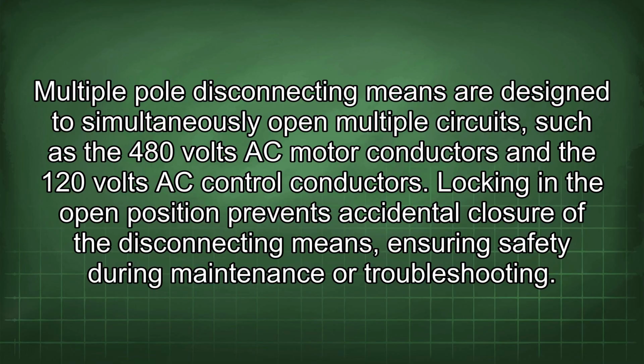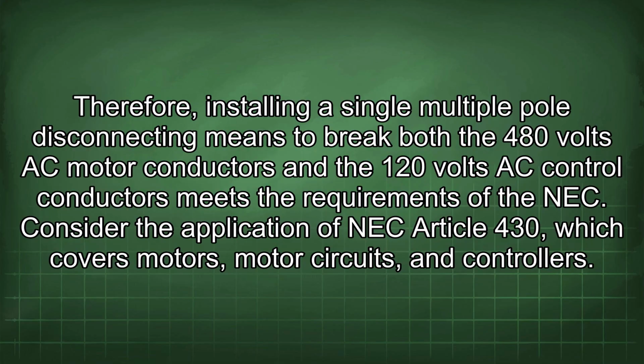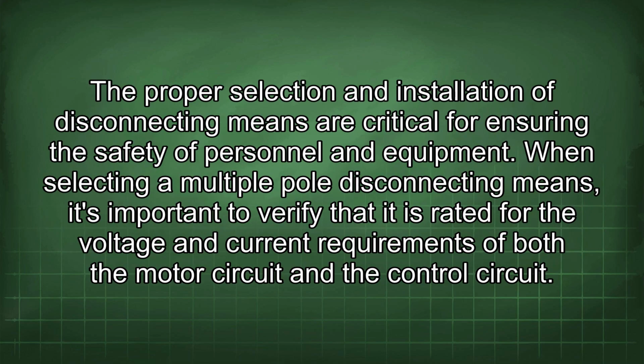Locking in the open position prevents accidental closure of the disconnecting means, ensuring safety during maintenance or troubleshooting. Therefore, installing a single multiple pole disconnecting means to break both the 480 volts AC motor conductors and the 120 volts AC control conductors meets the requirements of the NEC. Consider the application of NEC Article 430, which covers motors, motor circuits, and controllers. The proper selection and installation of disconnecting means are critical for ensuring the safety of personnel and equipment.